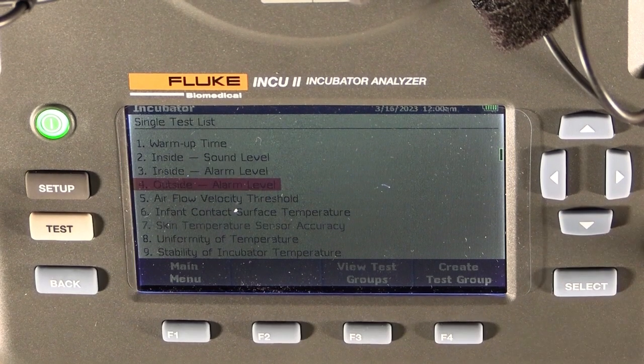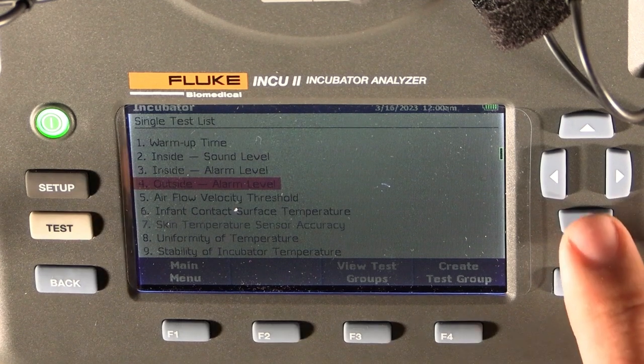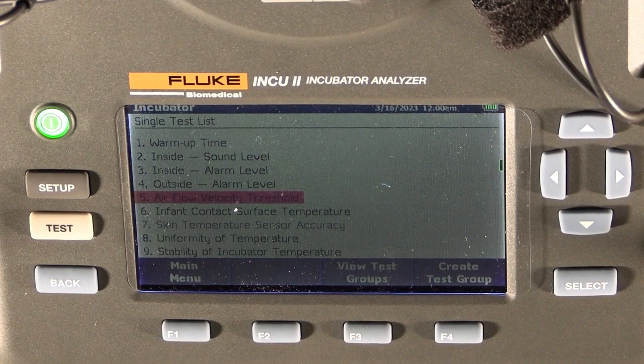The next one is our outside alarm levels. In this case, we will be moving the unit with a microphone 3 meters away from the incubator, and we'll be closing the hood of the incubator to keep the fan noises on the inside, and we'll then measure the environmental noise outside the unit. Number 5 is our airflow velocity threshold. During this test, we'll be removing all the other sensors and placing the airflow sensor in the center of the hood and perpendicular to the airflow, and then we'll leave it and get our stable reading of what our airflow threshold is.